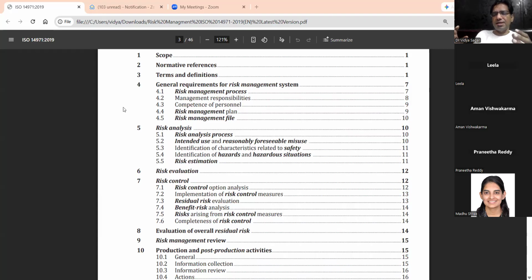Because in the beginning I told you risk management is not just about the device, it's also about your QMS. See, if you don't have any supplier controls, design controls, production controls and all this, at the end of the day, your technical specifications, during your design transfers, you will get a lot of things on technical specifications because your design outputs translate into design specifications. Those who are in R&D can understand it better. Madhu or Leela, those who are in R&D, they understand it. At the end of the day, the design outputs translate into technical specifications of the product or the device. Sometimes they may go wrong. So that's why the design phase is such a crucial thing.